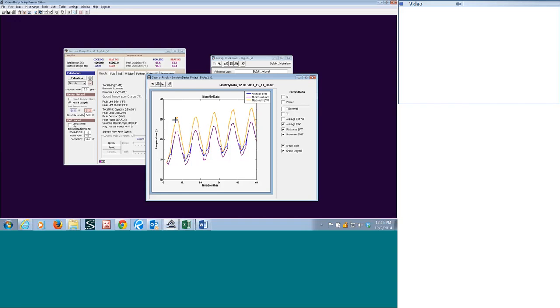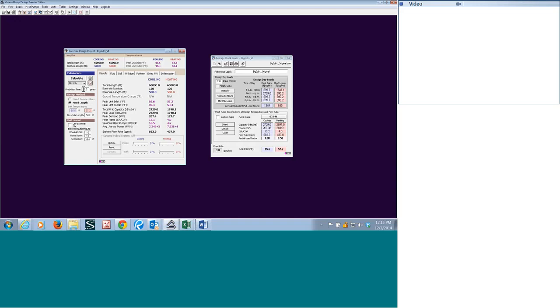And we've also got a lot of trend data showing that the actual ground loop temperature, if everything was evaluated and designed correctly, this heat creep is a rare thing. I'm not going to say it could never happen, but in most cases, it's wrong. It's only in theory. So what we're going to do is look at this from the perspective, if the loop field is overheating and everything is okay on the surface, what could be the issue? Well, the first thing that I would assume is that maybe the loads were not correctly calculated. And in this case, after looking at the inputs on the loads and everything, we determined that to be true.